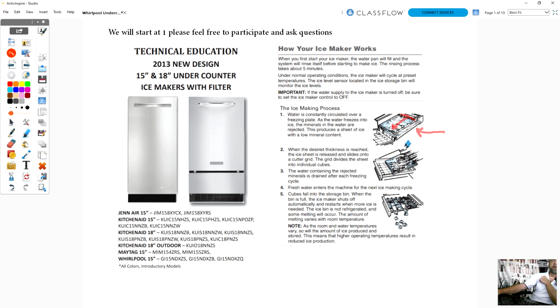Once the ice is ready, the unit does what they call a bypass. A valve opens up and lets the refrigerant from the condenser go straight to the evaporator, which warms it up. The ice sheet slides down into this metal cutting grid, and the cutting grid gets warm and cuts the ice. This cutting grid is low voltage and not very hot, because if it was, it would melt the cubes before they even reach the bin. So that's the basic operation: water circulates over the evaporator, it cycles that slab, and then cuts it into pieces.